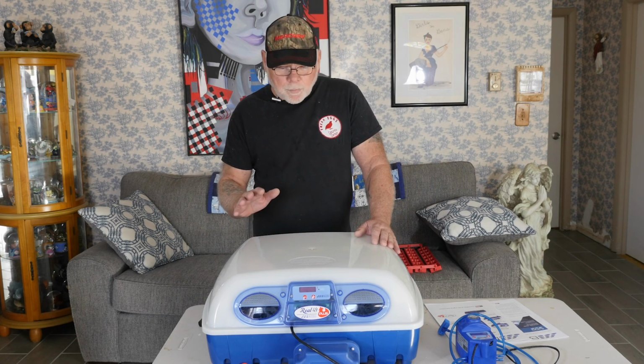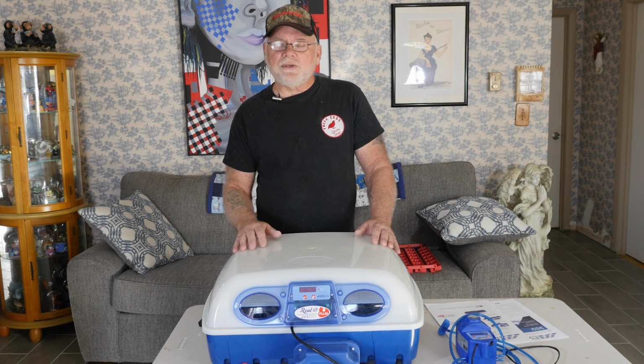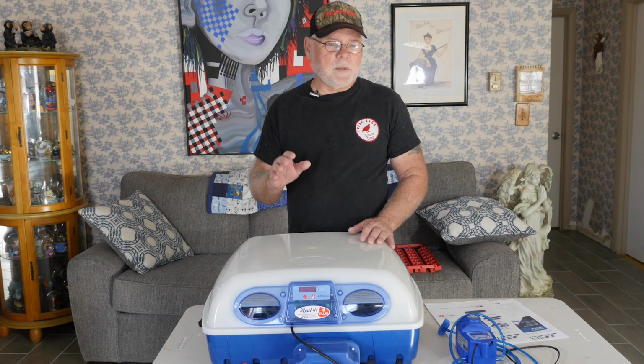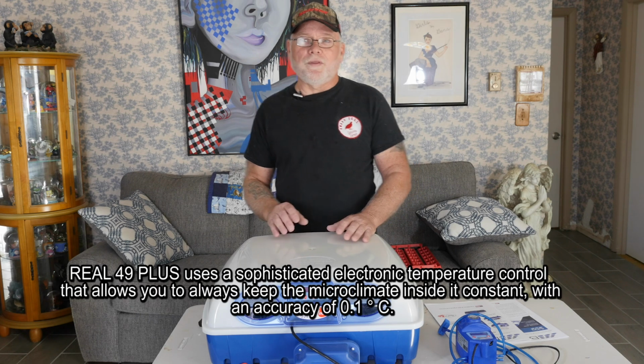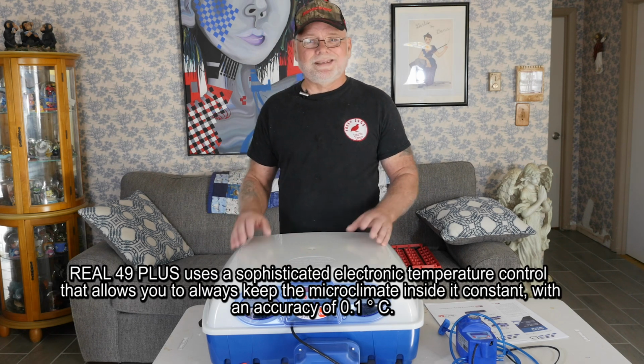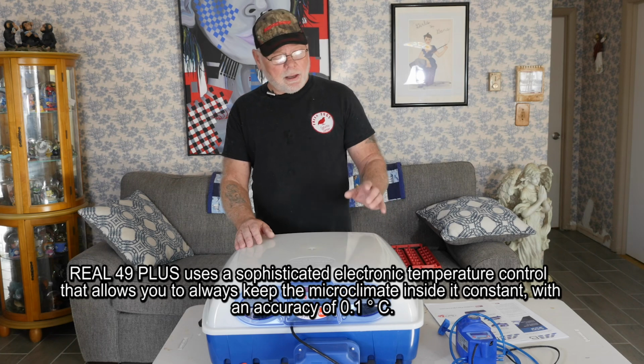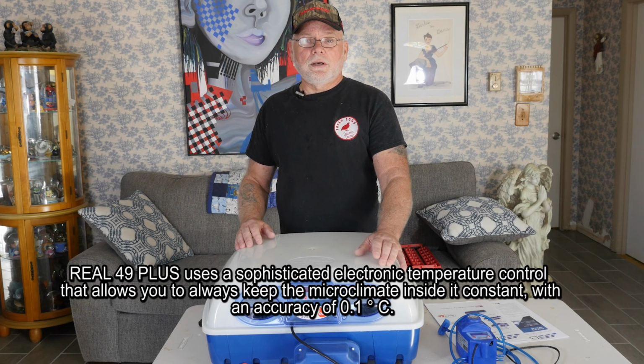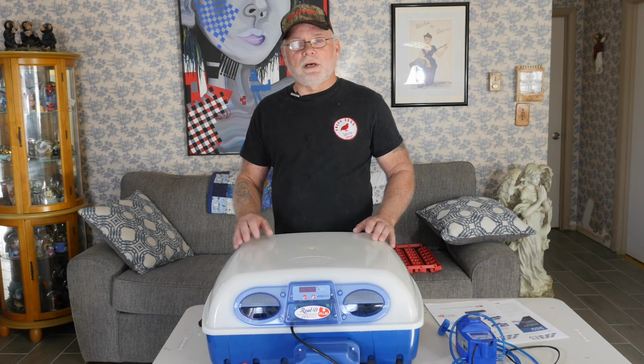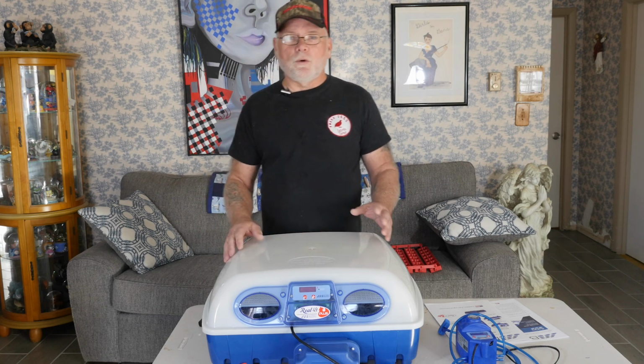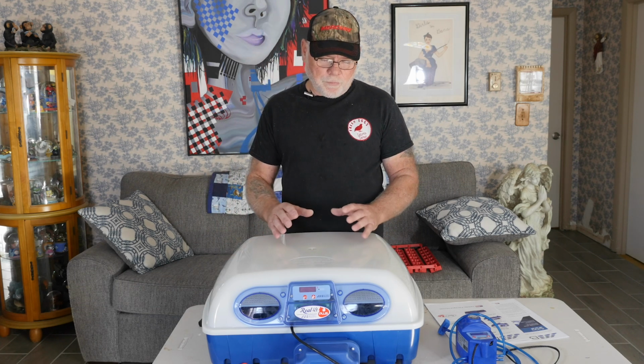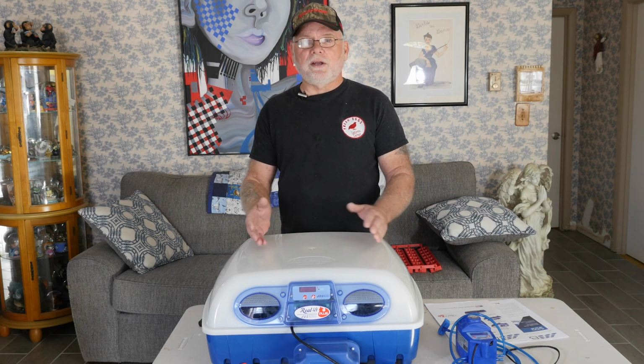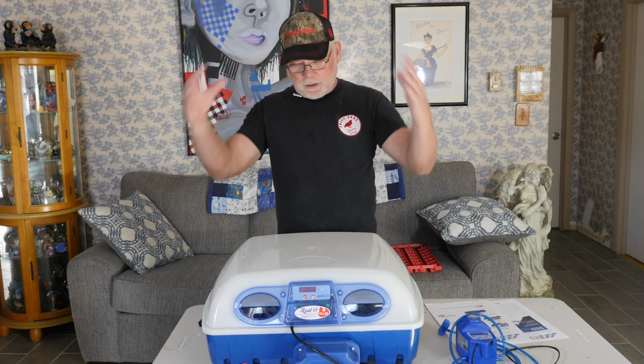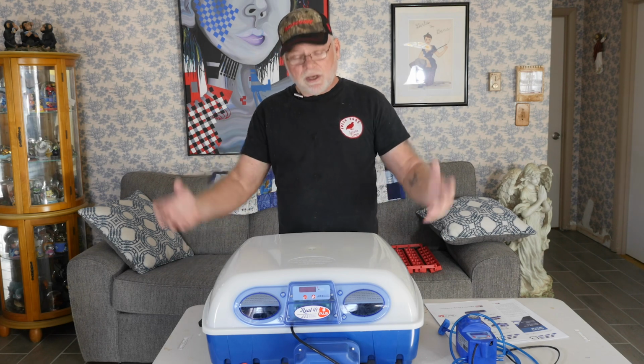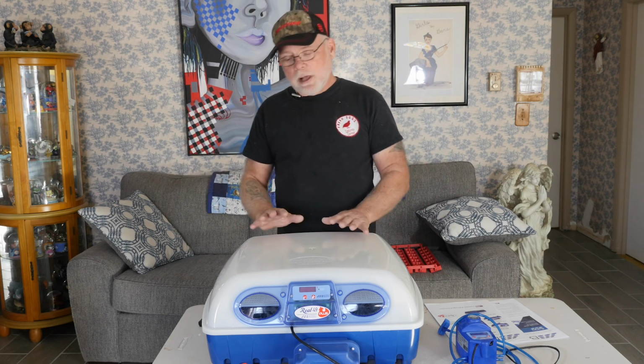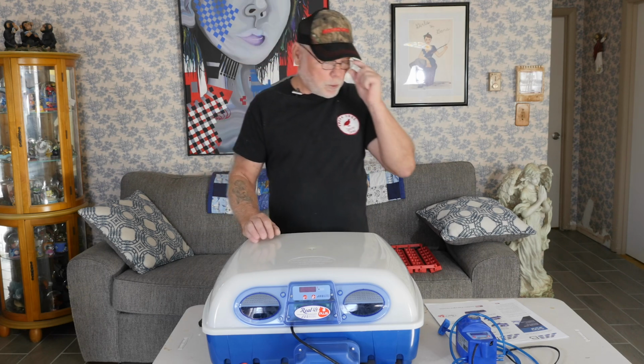Another thing I really like is the accuracy of this unit. Borotto says it's accurate within 0.1°C, which is pretty darn accurate. Like I said, I tested the temperature in different areas of the incubator and found no warm or cold spots. The way the circulation fan draws the air up and pushes it back down around the sides, it's a constant flow, so I really don't see how you could have any warm or cold spots.